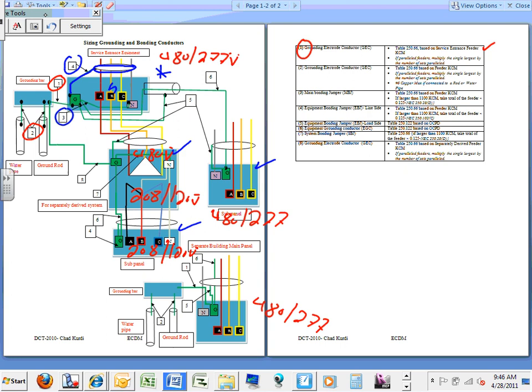Any question about number 4? Number 4 might be confusing. Number 4 appears in a few locations. Size is the same as 3. Number 4 is also right here, but not line. Number 4 gets to this line. So you're saying number 4 is sized exactly like number 3? Yes. Number 4 is the equipment bonding jumper on the line side. Number 5, guys, equipment bonding jumper load side.